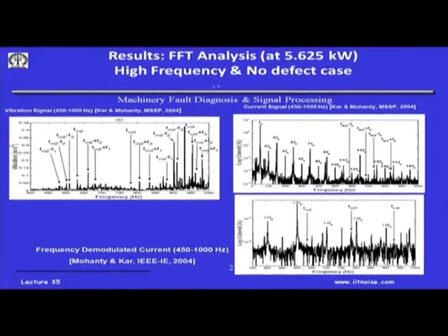Of course, we also saw the high frequencies because we wanted to see around the gear meshing frequencies. The earlier case was 0 to 100 hertz, but if you will recall, the second gear meshing frequency is around 630 hertz. So, you will see a lot of sidebands around the gear meshing frequencies. Of course, they look very gibberish right now, but if you have the right kind of frequency estimation and frequency detectors in your algorithm, and I will only be looking for these frequencies and monitoring their amplitude, you will do a good job in using motor current signature analysis.